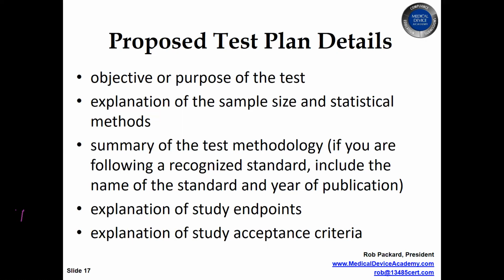3654, which is the Declaration of Conformity. You're not required to give them the list of all the harmonized standards or recognized standards for a pre-sub. You can if you wish, but I usually don't bother filling it out for the pre-subs. Say, here's my testing plan, and I want feedback from the FDA on the testing plan. Then we'll have an explanation of study endpoints. For this proposed test plan. What are going to be the endpoints for testing? And what are going to be the acceptance criteria? So these are the basic things we want in our test plan, whether it's an official recognized standard or something we've developed in-house.